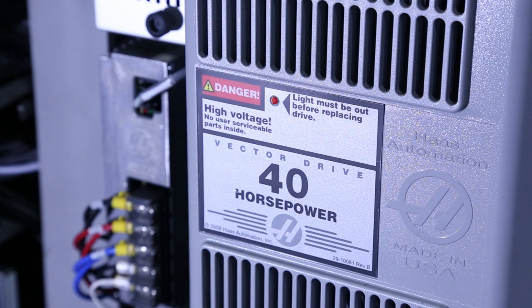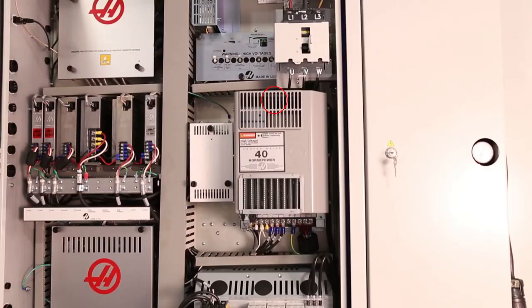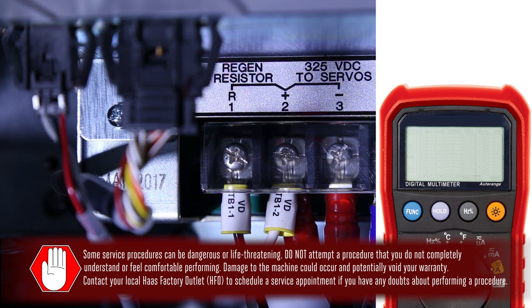Before you start, set the main circuit breaker to the off position and wait until the red LED on the vector drive goes out. If the LED is still on, there may be a lethal level of voltage on the DC bus. Before you perform any operation on the vector drive, make sure the LED has gone out completely.